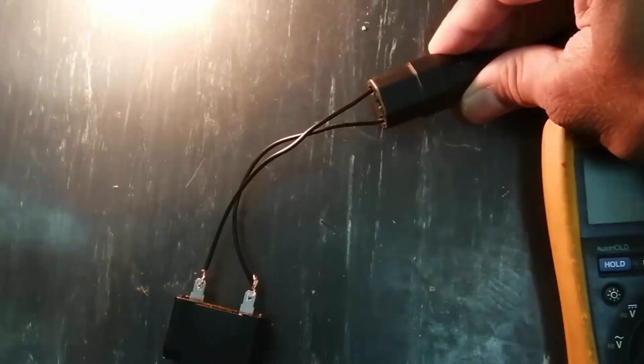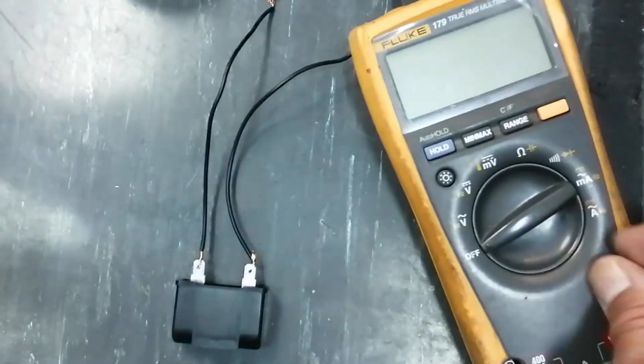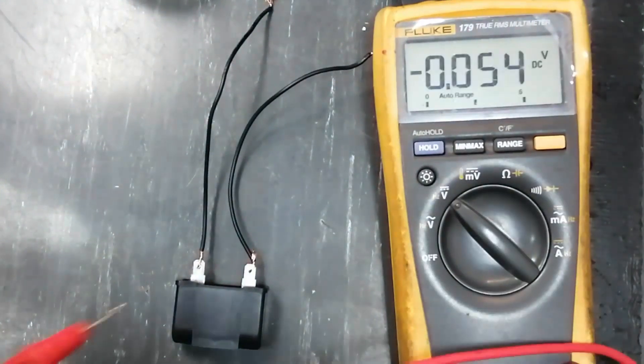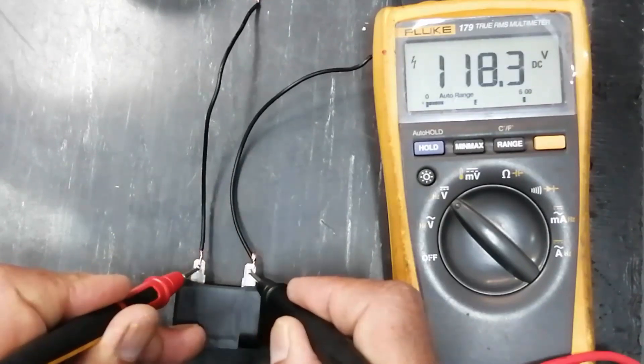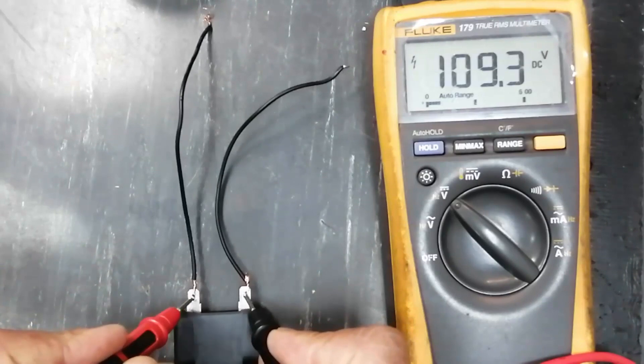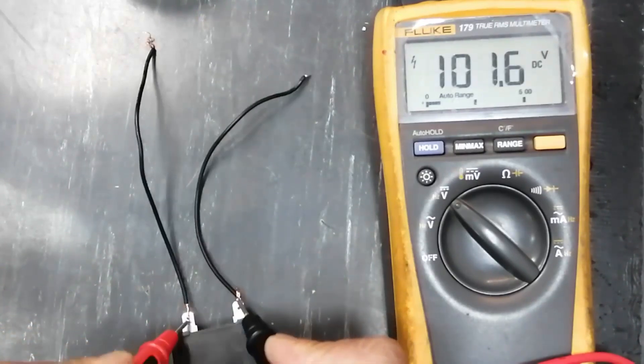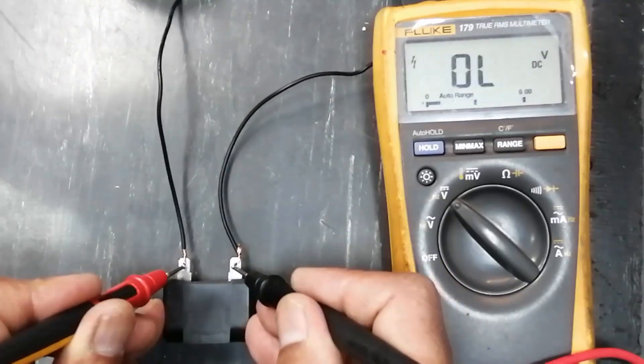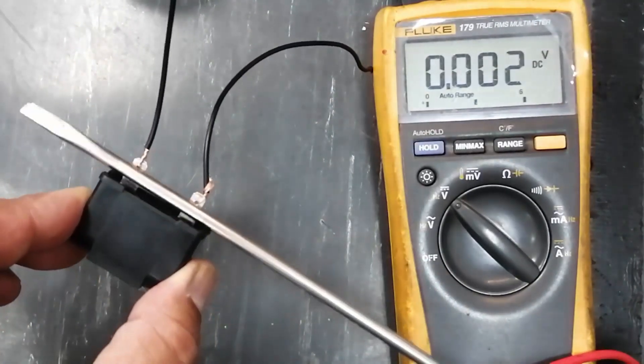Set the multimeter to DC volt and connect to the terminals. We can see it has 116, 115 volts, so it is charged. Still, I removed it and it has voltage. So this is the reason we always have to make short.